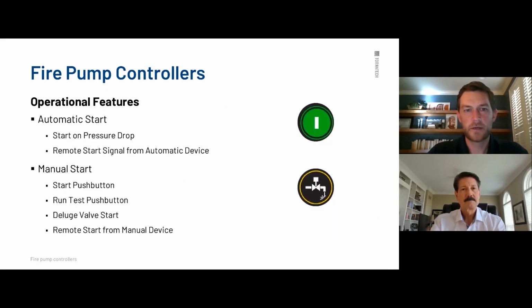So to get into some of the operational features for fire pump controllers, the two most common ways to start are automatic start and manual start. Automatic starts are going to be based on a pressure drop. That's the way the majority of the systems are set up. Using a pressure transducer, whenever there's a drop in the system pressure, the pump will start up and run until it gets to its cutout point. And then somebody will need to come and manually stop it if you don't have an automatic stop enabled.